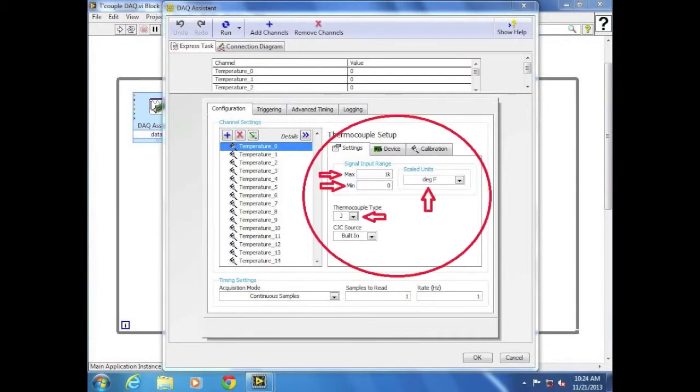Under the settings sub-tab, ensure that signal input range max is set to 1k and that min is set to 0. Scaled units is to be set to degrees Fahrenheit, and thermocouple type is set to J.